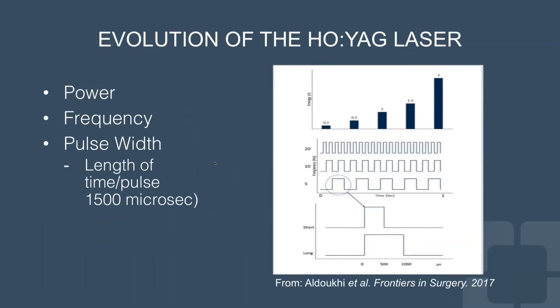Over the last few years, there has been significant evolution in holmium YAG lasers. We were first able to control power and frequency; most early machines were low-frequency because they were built from a single rod. More recently, in the last 5 to 10 years, we've been able to modulate parameters such as pulse width, which controls the length of time per pulse. With multi-rod generators, we can now have higher-frequency machines with current-day frequencies over 50 hertz.